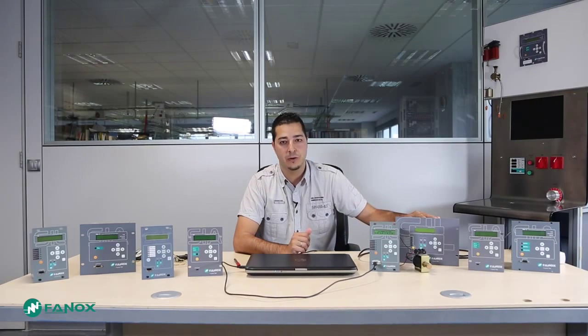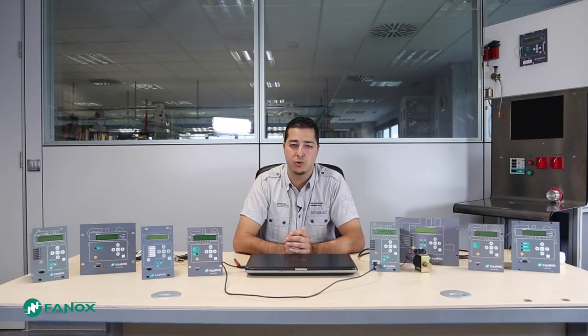Fanox medium voltage protections have a common and handy interface that allows us to set up and configure the device both by their human-machine interface or by communications with the communication program SICOM. Depending on the relay model, we will have a serial RS-232 with DB9 connector or a USB port.